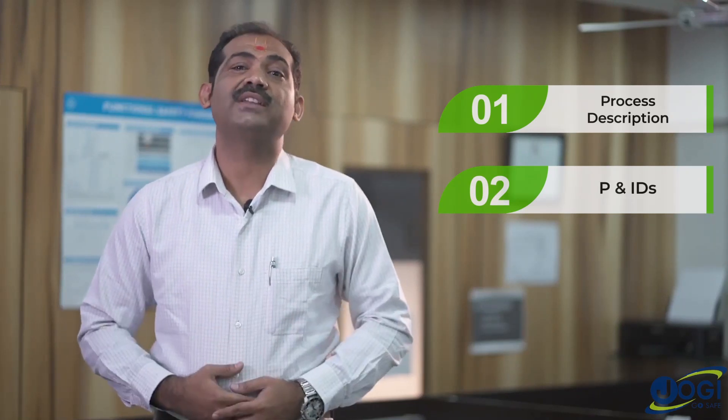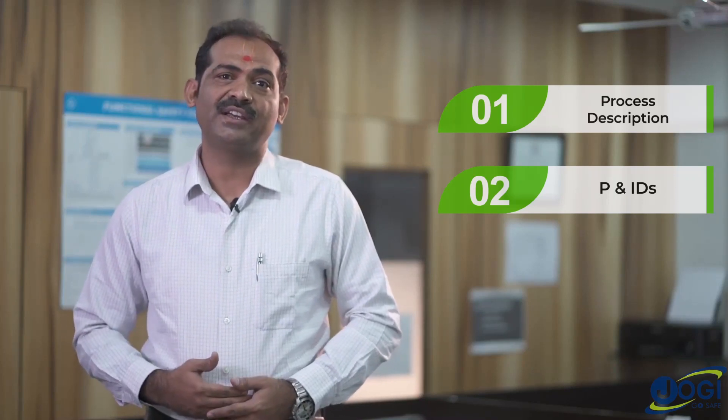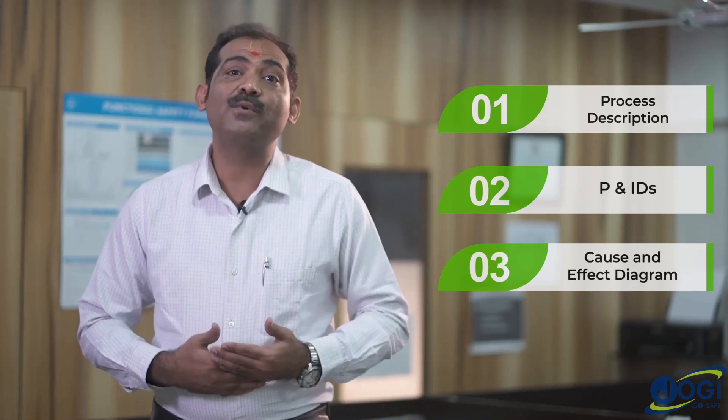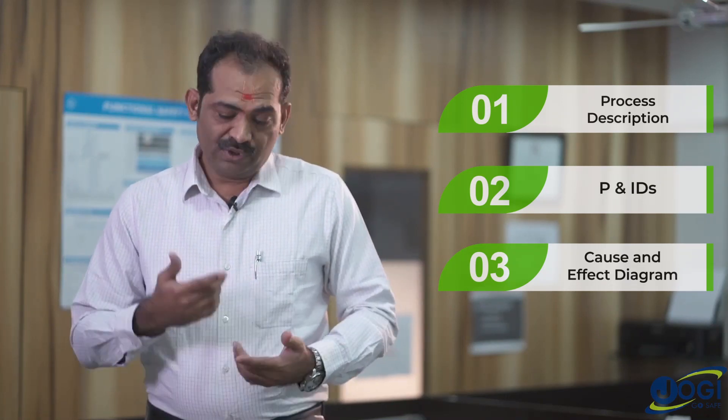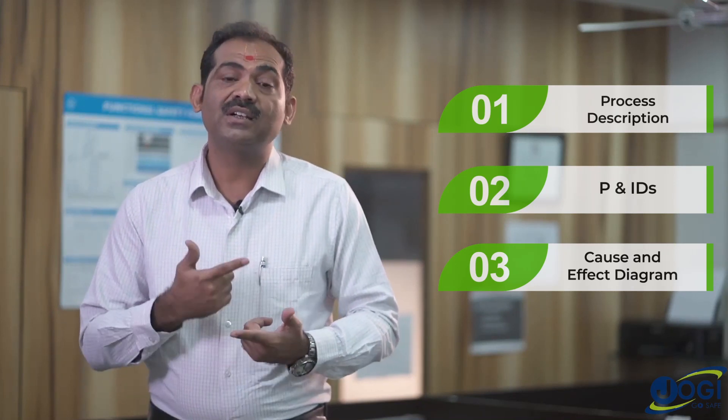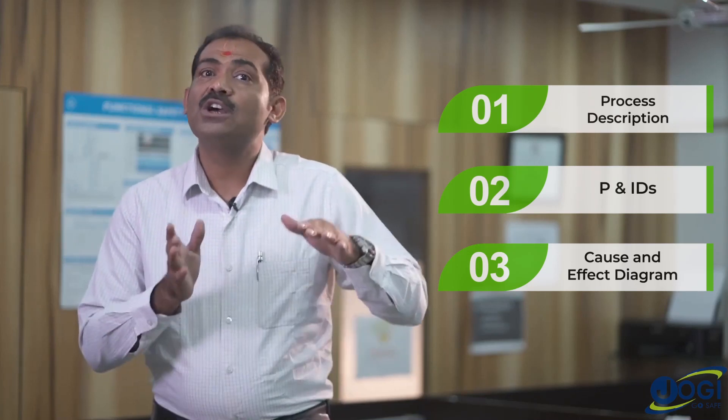Let us understand what the prerequisites are to conduct this hazard study. The first requirement is a detailed description of the process. The second is the P&ID, or piping and instrumentation diagram. The third, which is very important, is details about alarms, trips, controls, and interlocks — also called the cause and effect diagram. These three are the basic requisites; in some cases specific documents like layout or design documents may also be referenced.